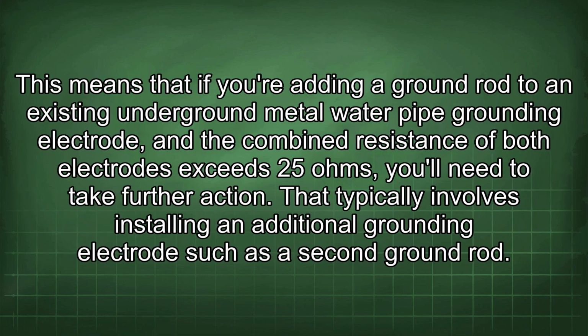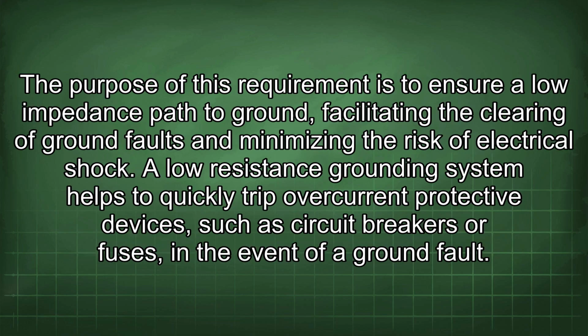This means that if you're adding a ground rod to an existing underground metal water pipe grounding electrode, and the combined resistance of both electrodes exceeds 25 ohms, you'll need to take further action. That typically involves installing an additional grounding electrode such as a second ground rod. The purpose of this requirement is to ensure a low impedance path to ground, facilitating the clearing of ground faults and minimizing the risk of electrical shock.